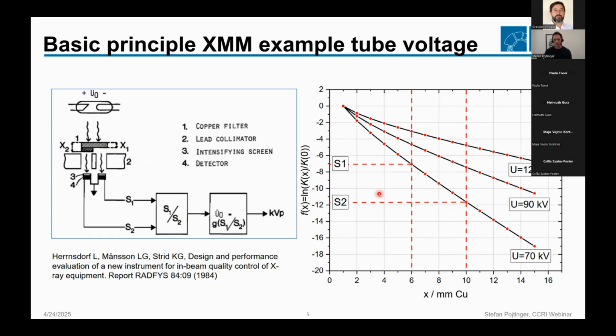And that's a starting point. Now you can start to think about, I could calibrate that, for example, for tube voltage. Well, if I know the tube voltage, I have some idea about the photon spectrum of my X-ray device. And then with that information, I could calculate a correction for energy dependence, and then automatically correct my reading of the silicon diode for the air kerma measurement based on that. And well, that's more or less what is done in modern devices.